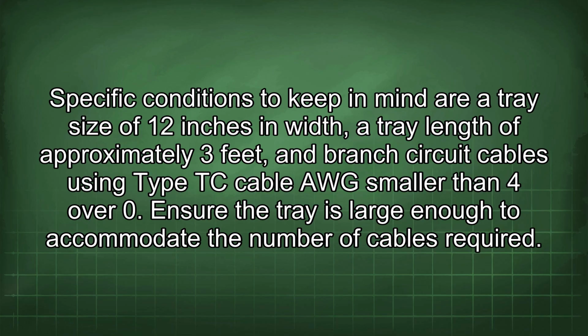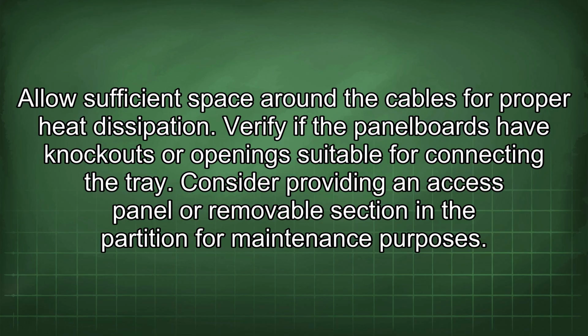Specific conditions to keep in mind are a tray size of 12 inches in width, a tray length of approximately 3 feet, and branch circuit cables using type TC cable AWG smaller than 4/0. Ensure the tray is large enough to accommodate the number of cables required. Allow sufficient space around the cables for proper heat dissipation. Verify if the panel boards have knockouts or openings suitable for connecting the tray. Consider providing an access panel or removable section in the partition for maintenance purposes.